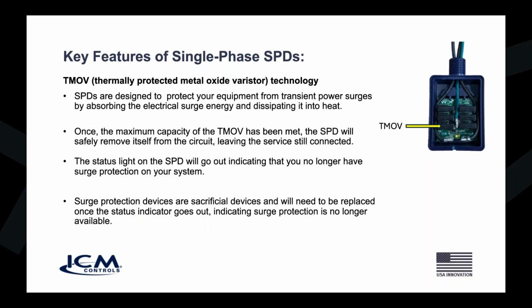Now, that possibility exists if your hit is so big that it exceeds the maximum capacity of the device. In this case, the 517A Lite, maximum surge can be 60,000 amps for a single hit. But remember, it can take many, many hits under that. So you could have your surge protection in for years without any damage, and then one big storm comes through and that could take it out. So it's not a one and done. I just want to be clear about that.